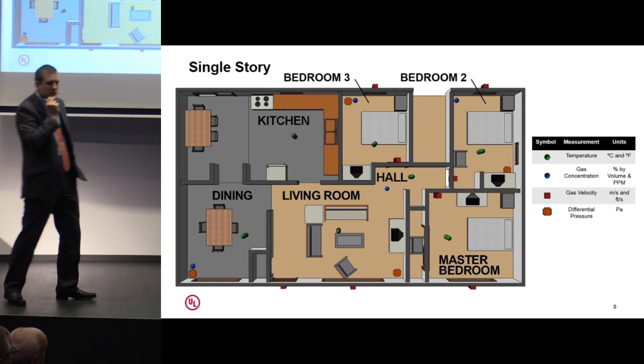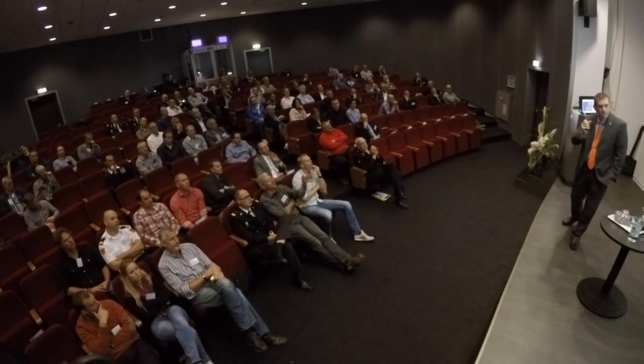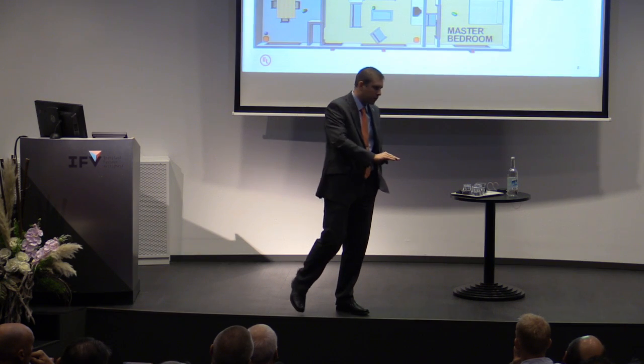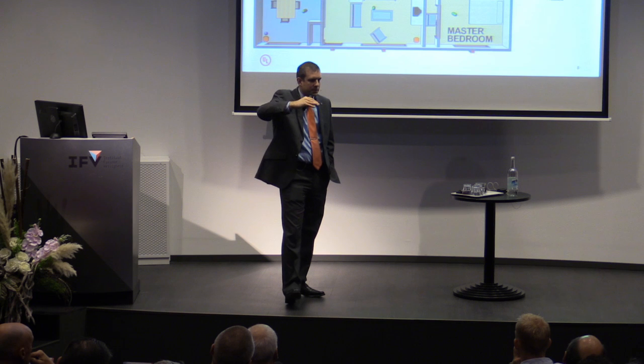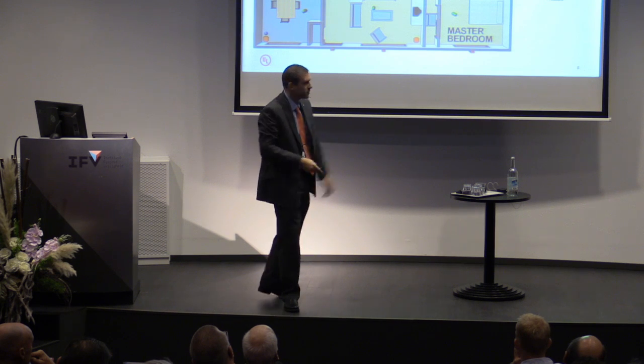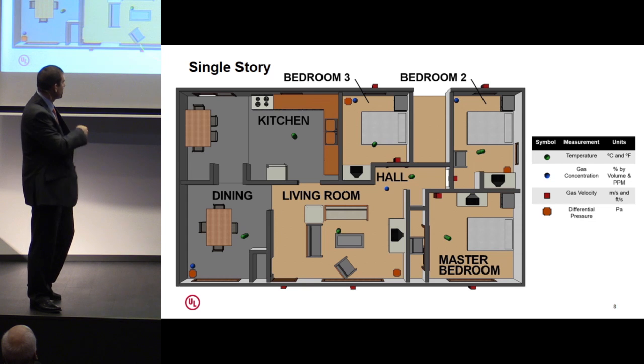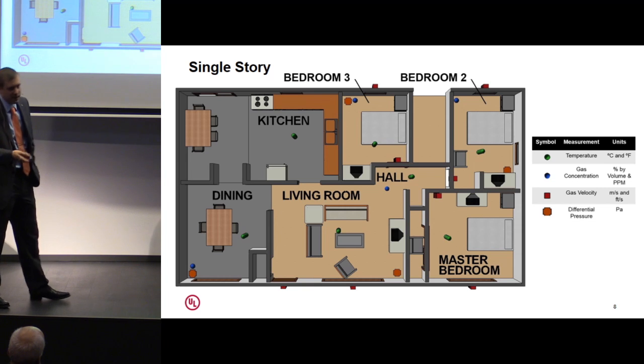Hans? You're mentioning differential pressure, but you only get one pressure point. The differential measurement is between the inside and the outside of the structure. And those are actually at 3 different heights. We measure the pressure 1 foot off the floor, in the middle of the structure, and 1 foot off the ceiling. The upper layer gases have a higher pressure than the lower point. That's one of the reasons we see buoyant flows in structures. So we measure at 3 different heights to try and put that all together. Coincidentally, with the fans pressurizing the structure, all 3 of them are within about half a Pascal of each other. So in reality, they're within the error of my measurement, so I can't really determine a difference there.